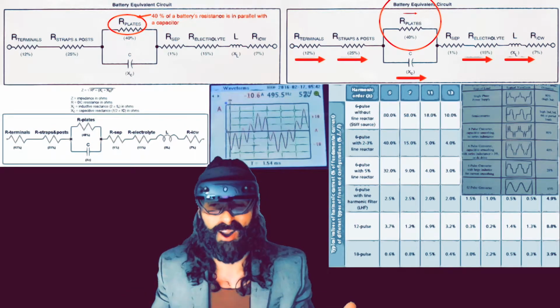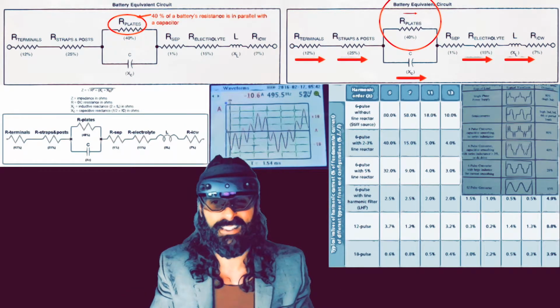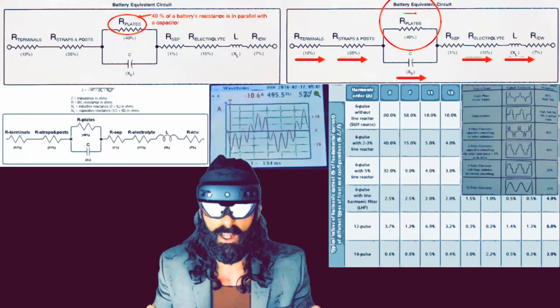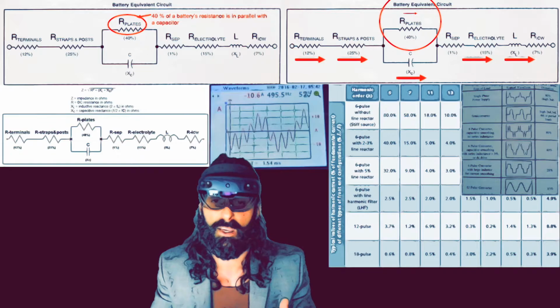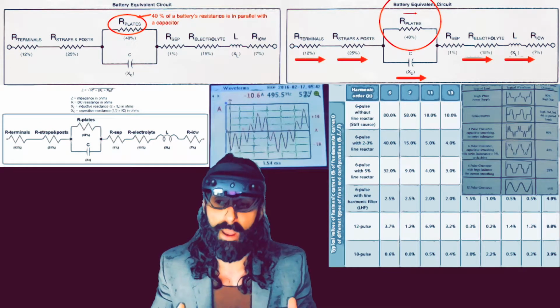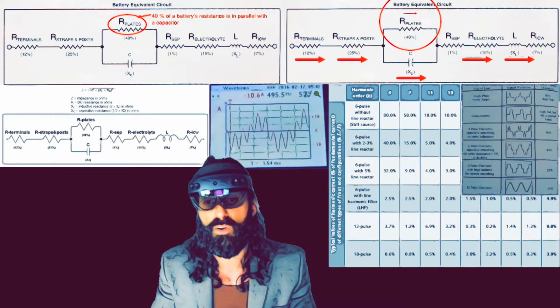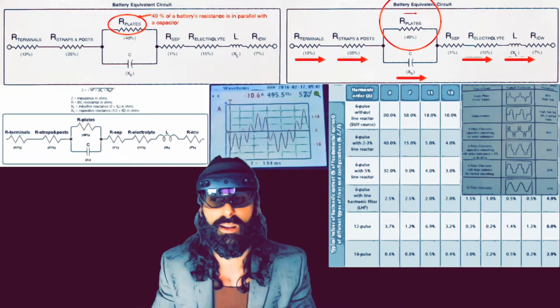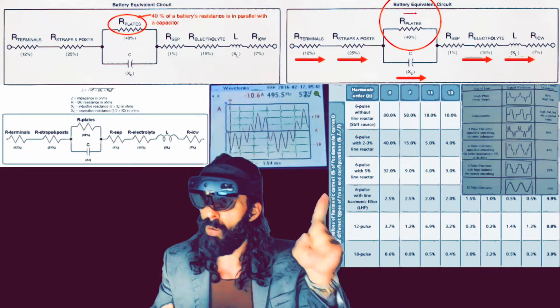So you see a lot of monitoring out there that is implementing AC impedance, AC conductance, because it's very, very low cost to develop and implement out in the field. DC current is expensive, the load banks are expensive, and it's difficult to integrate that. There's a lot of patents out there that people hold that you can't integrate and design appropriately. So let's talk about noise really quick.